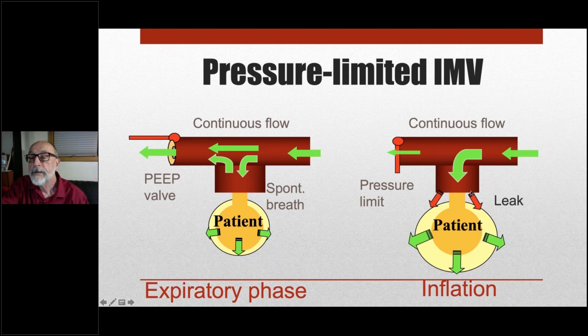And the volume delivered is proportional to the pressure within the circuit and the compliance of the lungs. So pretty straightforward. And we don't worry about a leak around the endotracheal tube because there's plenty of fresh gas available to maintain pressure within the circuit. And it was the ease with which we could ventilate in the face of large leak around the endotracheal tubes, and the conviction that pressure is the most important factor in lung injury. I refer to that as barophobia. But it turns out that volume is what we should fear more than pressure, as I hopefully convinced you.